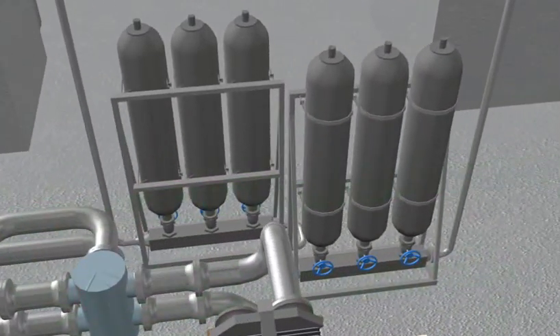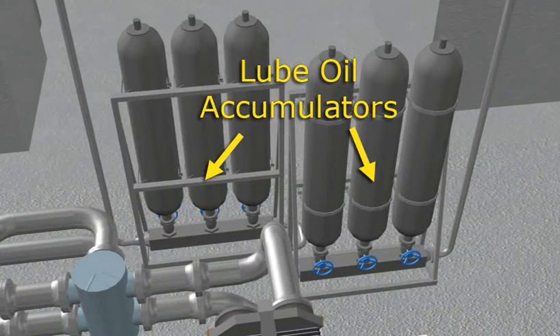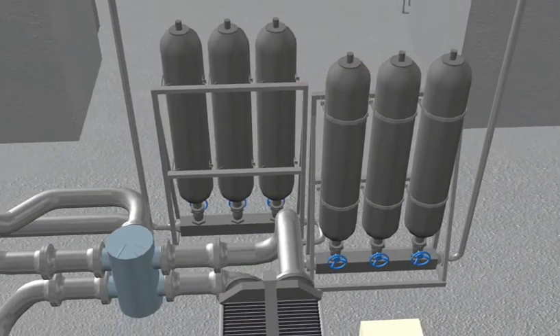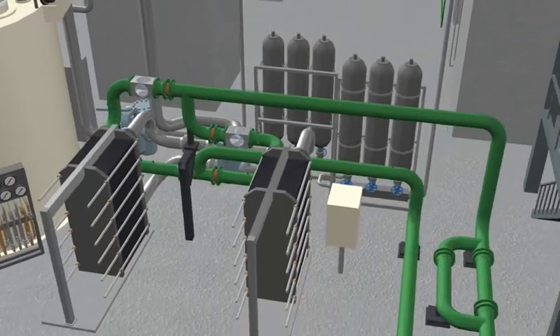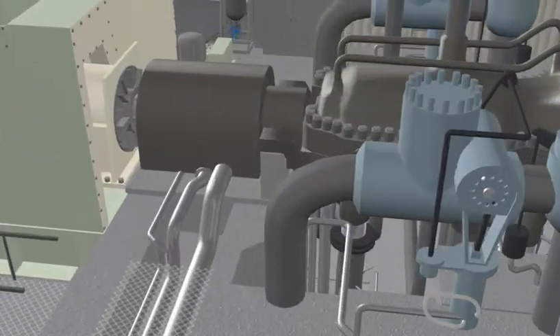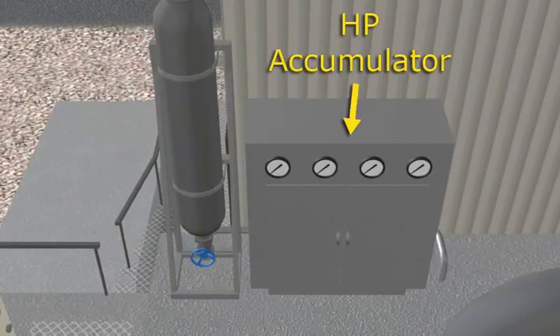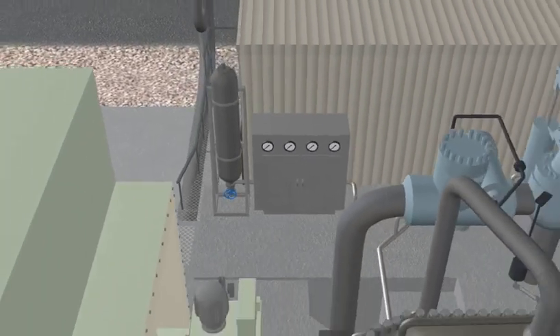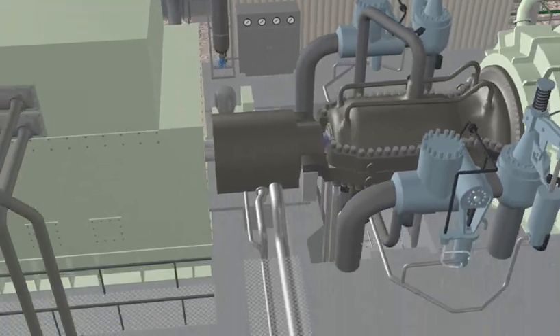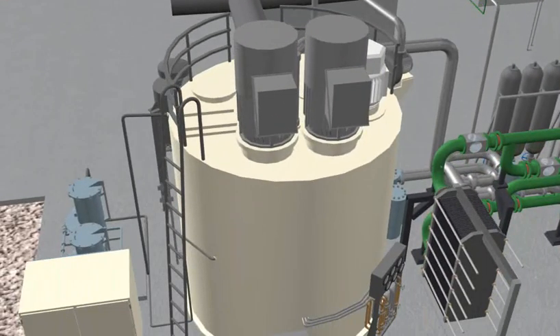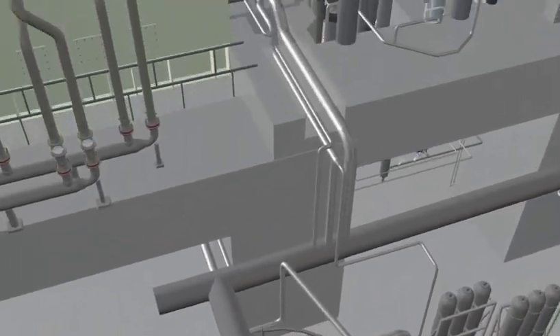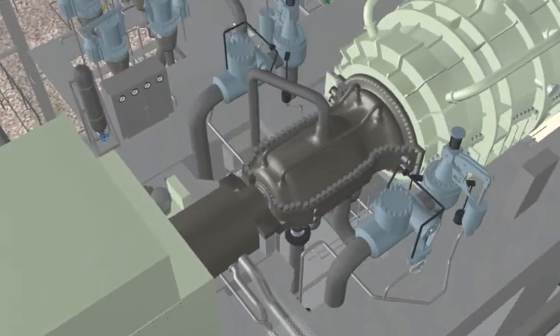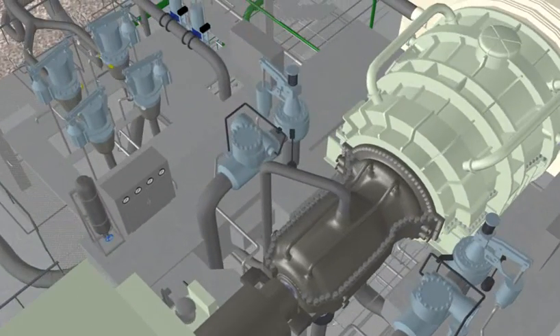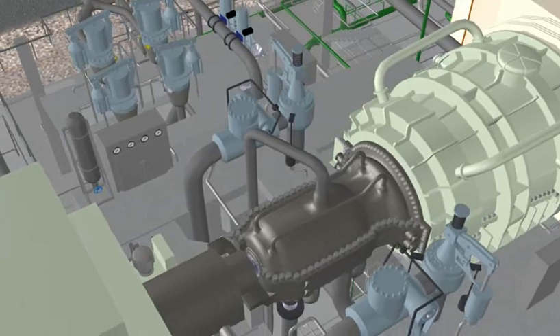The lube oil accumulators help dampen any pressure surges in the oil supply to the journal bearings and one thrust bearing in the turbine generator package. The high pressure accumulator dampens any pressure surges of the oil going to the main stop valves or governing valve servos. High pressure oil comes from the high pressure sections of the main and auxiliary lube oil pumps and is used to control all control and stop valves on the three steam systems.